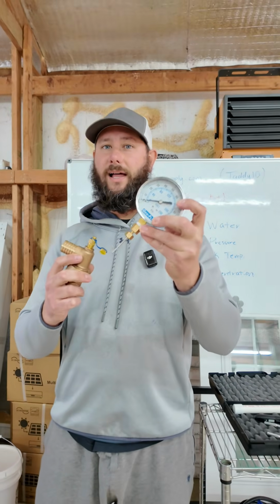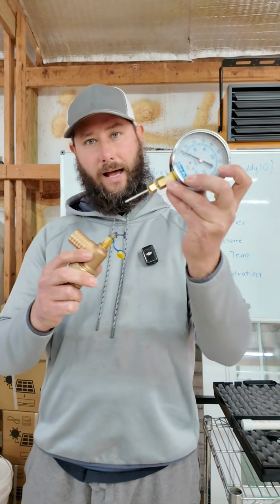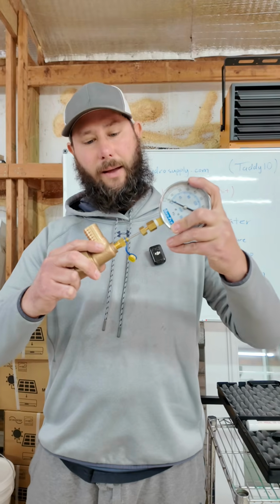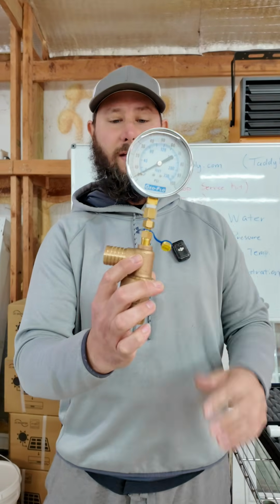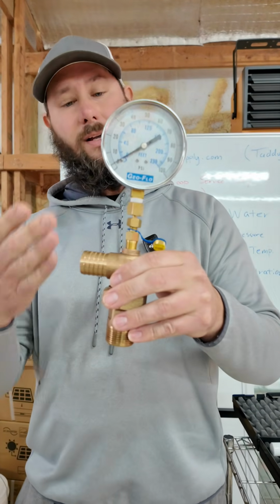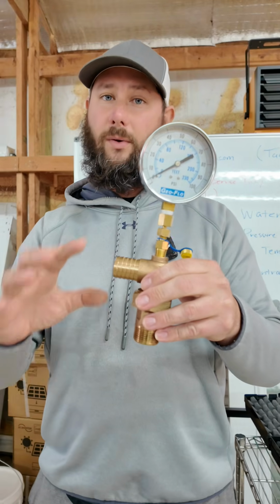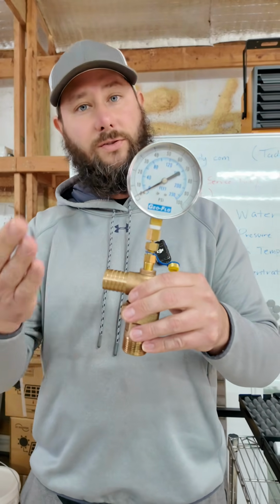The pressure gauge allows me to verify loop pressure. I use the needle adapter on the end, place it inside of a PT port, and then I can verify loop pressure, see the flow, make sure that we don't have low fill, and I can diagnose flow problems.